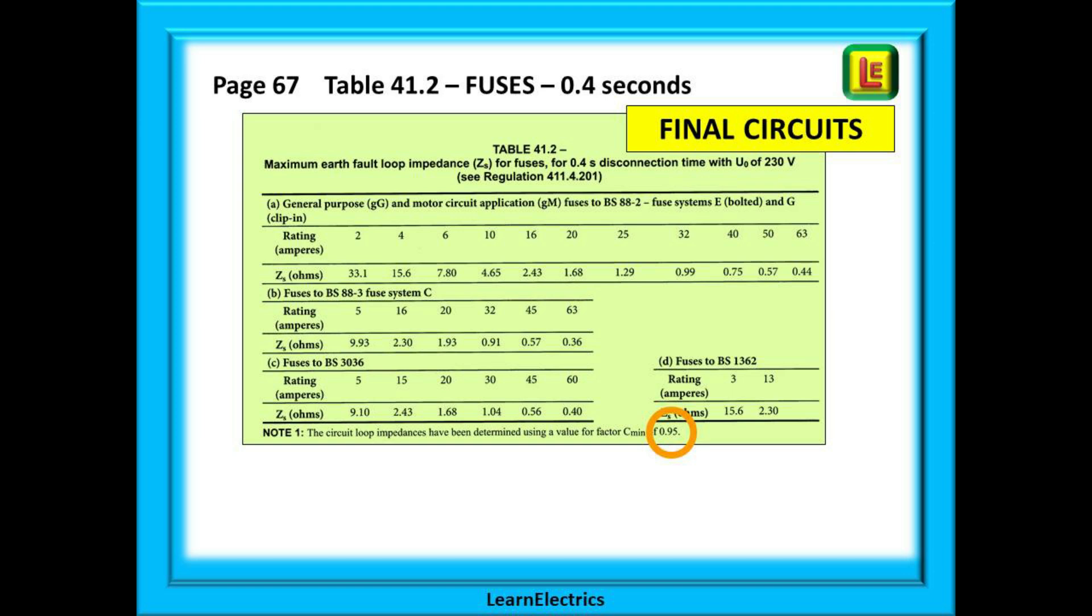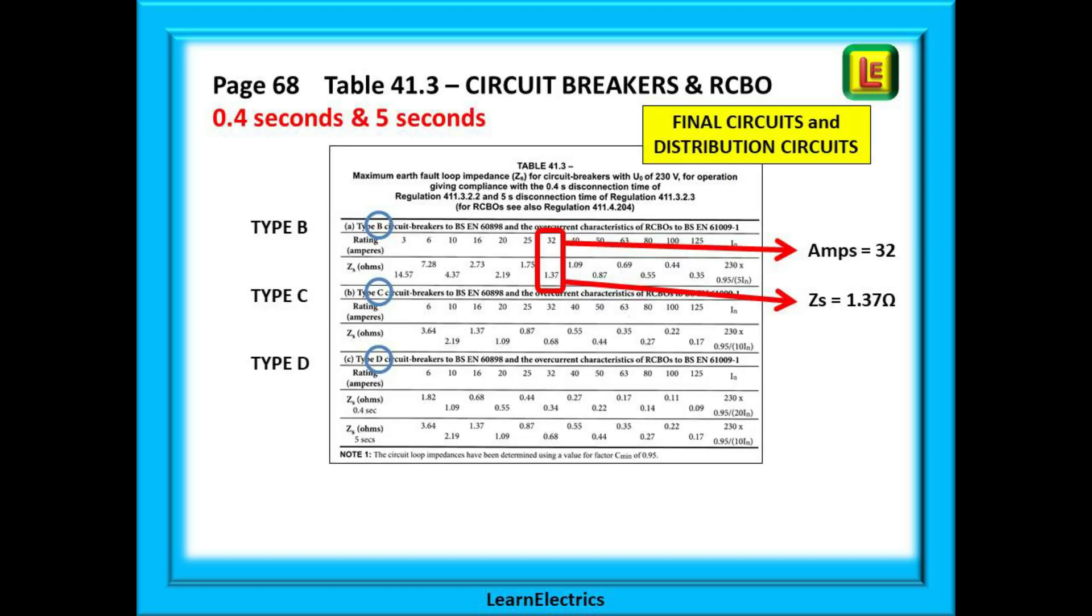Moving on to page 68, we find table 41.3 for circuit breakers and RCBOs. This table covers 0.4 second and 5 second disconnection times. So, it is for both final circuits and distribution circuits. Three types of breaker are available. Type B, C or D.